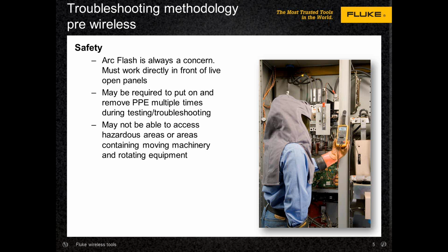The RF communications used in the modules today will actually talk for short distances through the electrical panels with the doors closed. So you can technically leave some of this stuff embedded or installed in the panel for some period of time and then monitor from the outside without even opening the panel door or removing the panel cover. Even for intermittents, that's great.